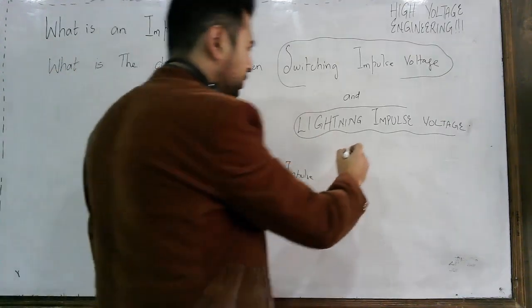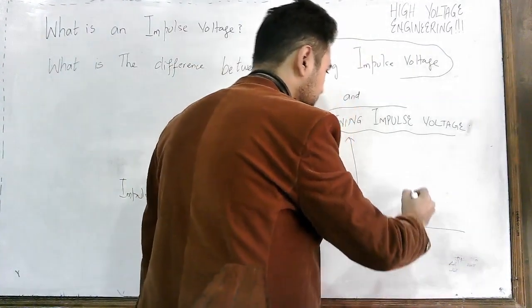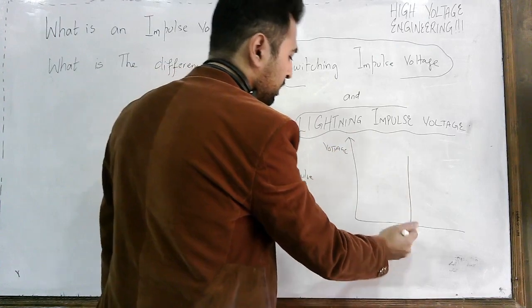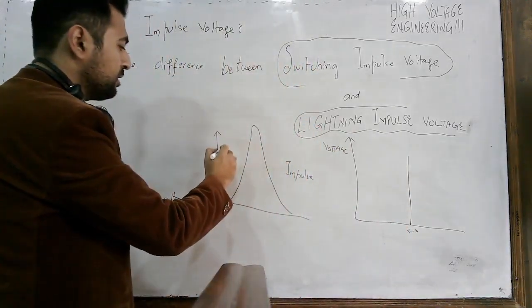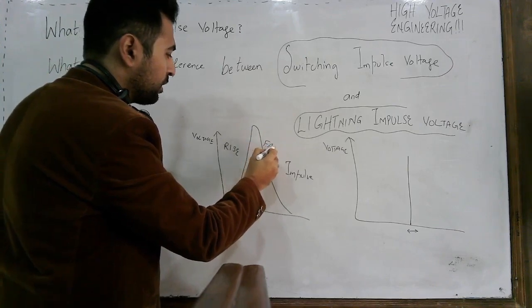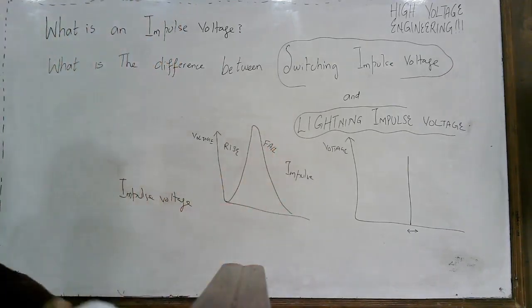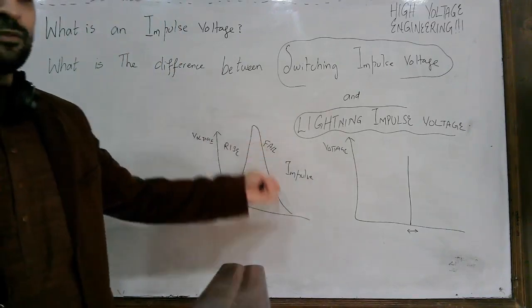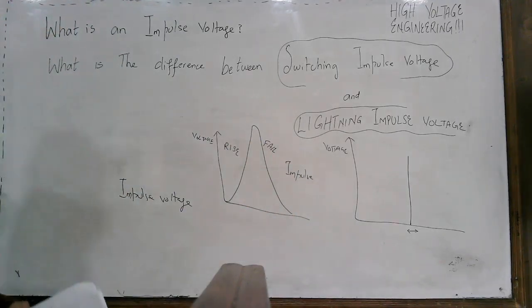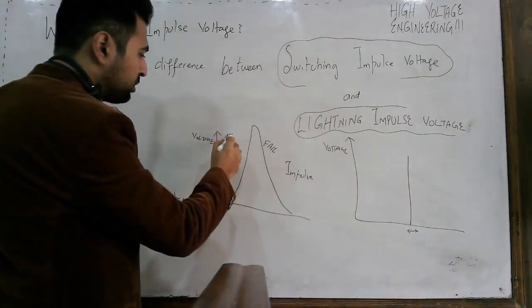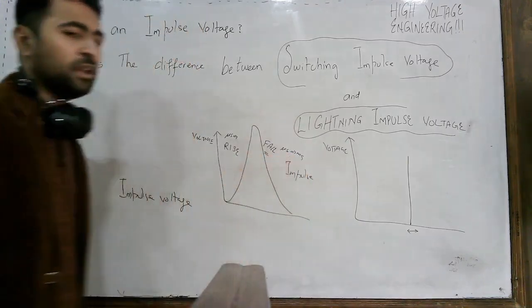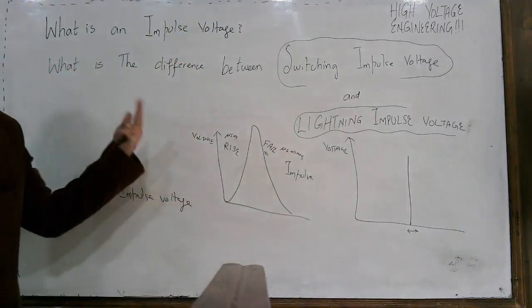In theoretical literature, impulse voltage is normally represented by a straight line. But practically, there will be some time for the rise of this voltage and some time for the fall of this voltage. This impulse voltage rises and then falls down to zero. Typically, the rise time is in microseconds and fall time may be microseconds to milliseconds. These are the practical characteristics of a lightning impulse voltage.